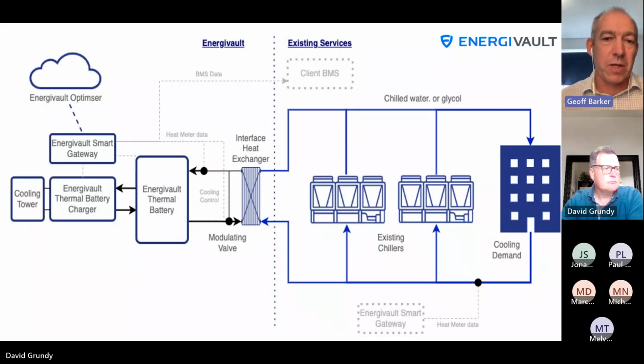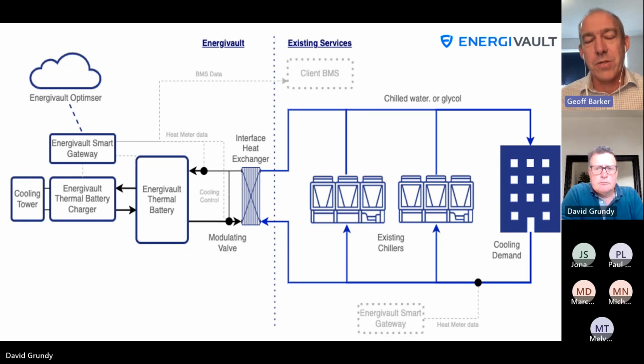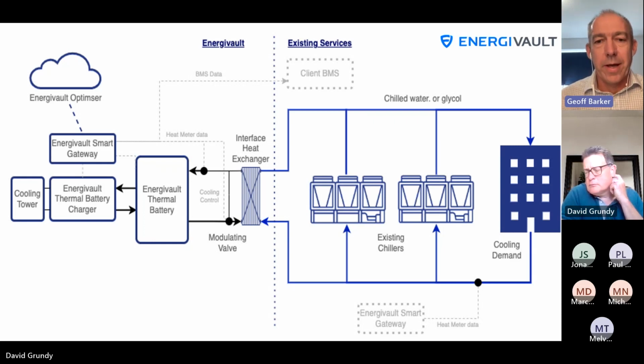On the right here you'll see what might be a typical system. In this case it's shown cooling an office block, but it could be a hotel, a food factory, a brewery, a data center - anywhere that has a chilled water circuit. Typically, the EnergiVault system will be connected into that via what we simply refer to as the interface heat exchanger, effectively decoupling the EnergiVault system from the glycol-based chilled water circuit, the existing circuit.